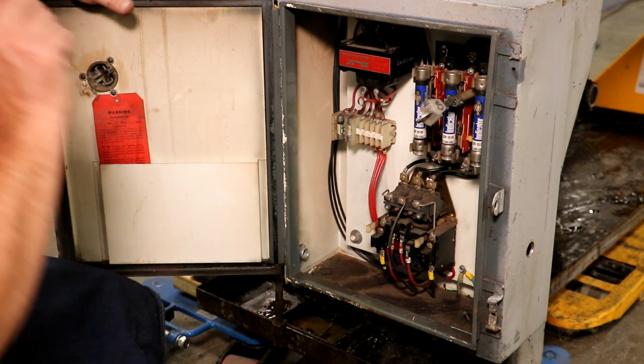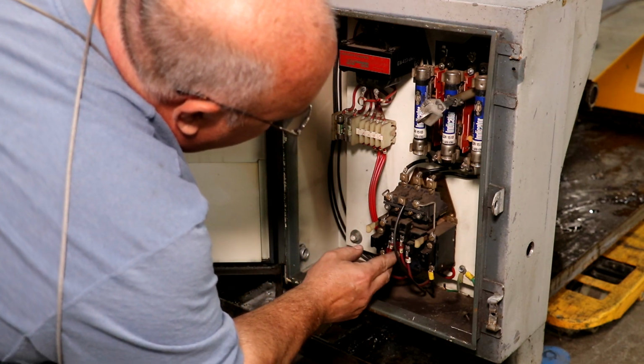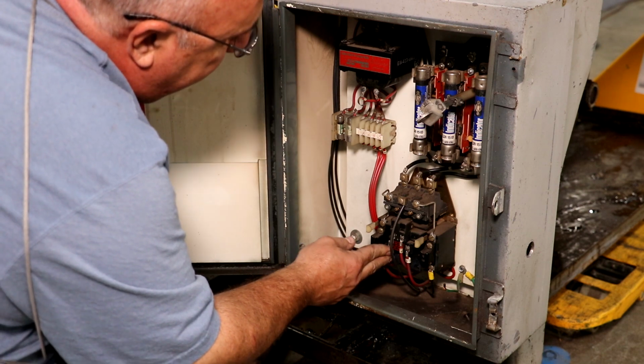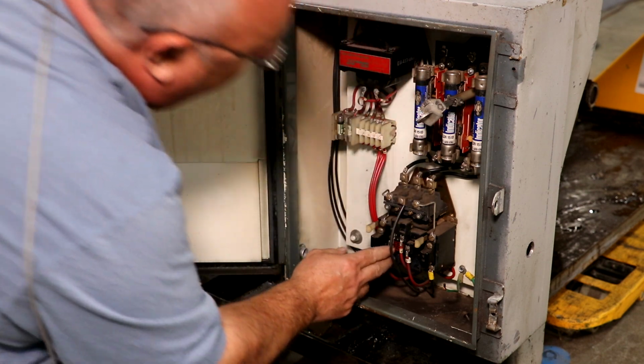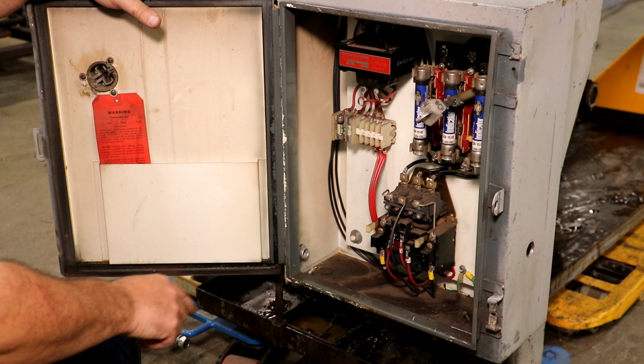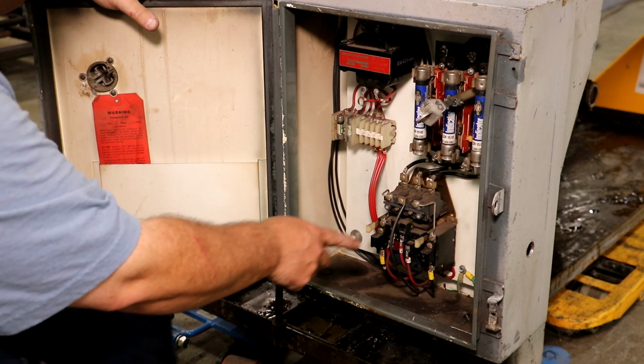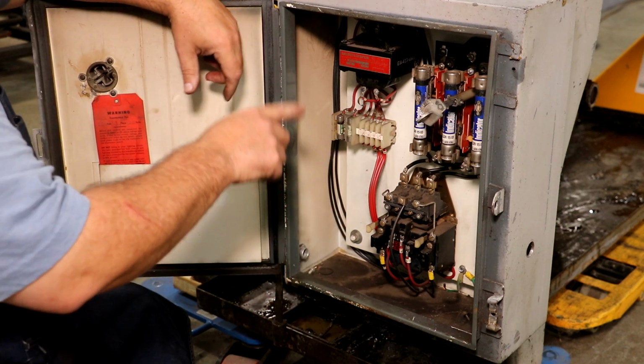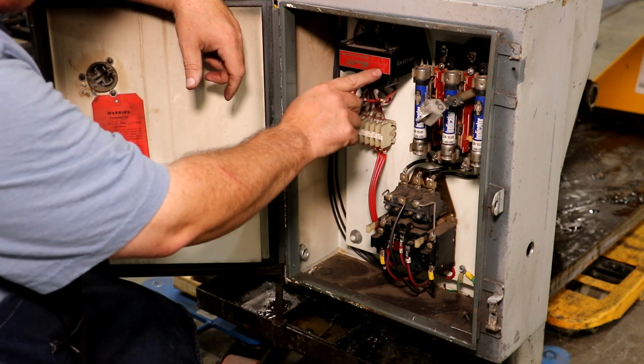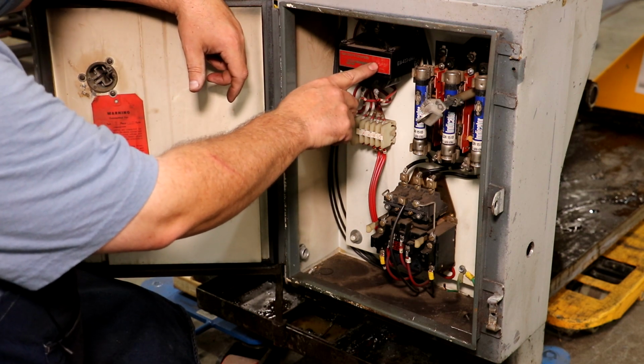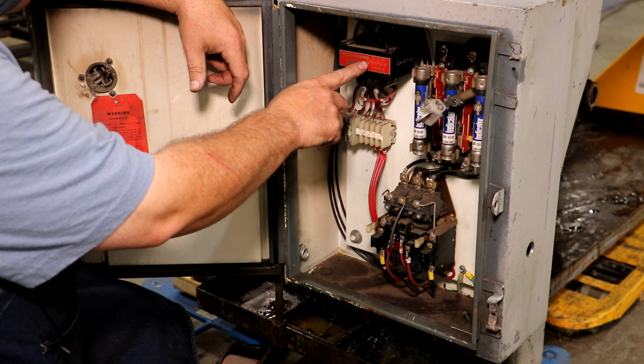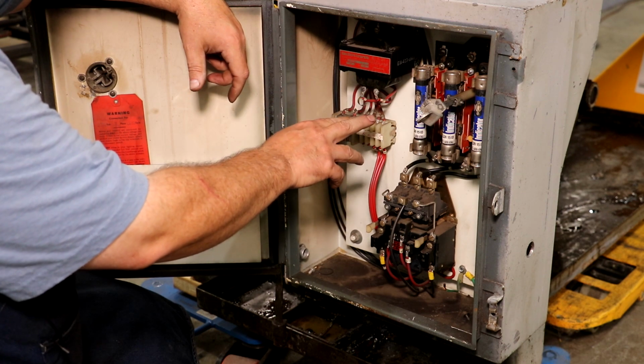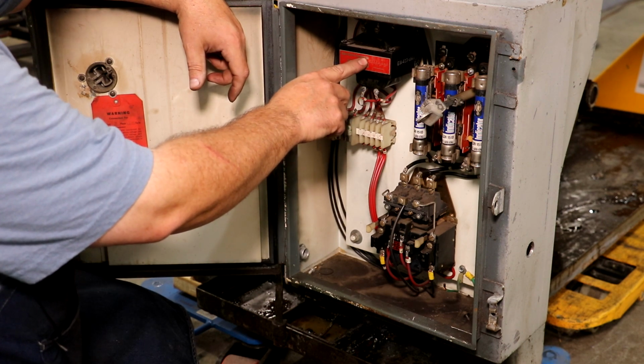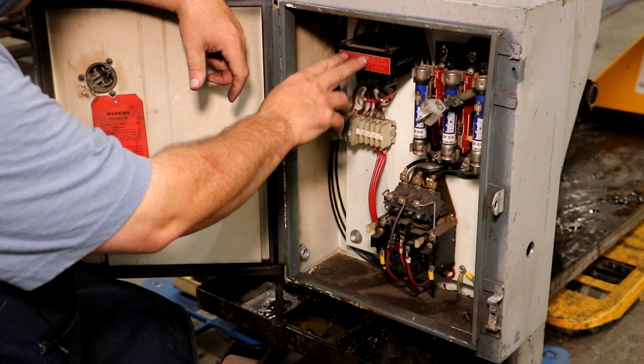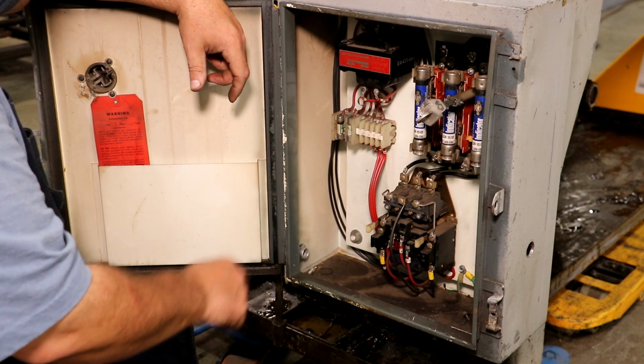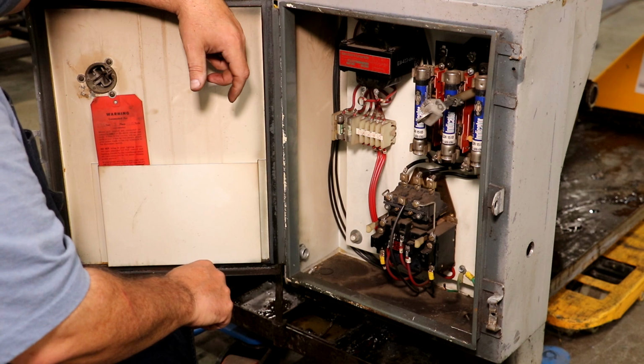Looks like it was a 110 volt coil, so we basically need 110 volts going to this coil. Now because I changed the voltage around, I'm probably going to have to rewire this thing, because it was being fed with 480 volts and stepping it down to 110. I'm now feeding it with 220 volts and will need to step that down, so we'll need to change something to make that happen. I'll have to look at the wiring diagram and figure that out.